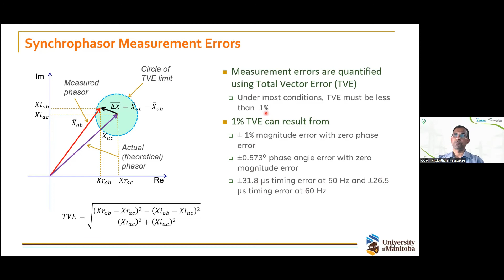To get some understanding of how tight the accuracy is, this 1% TVE can result even if the red line coincides with this one but there is a 1% error in the magnitude. On the other hand, if you have the same magnitude but a phase angle difference of 0.573 degrees, then it is exceeding the 1% error limit. This phase angle error corresponds to a 31.8 microsecond timing error for 50 Hertz, and for 60 Hertz it is even less than that: a 26.5 microsecond timing error can result in this error. So if you are building a PMU device, your time synchronization needs to be very, very accurate if you want to achieve this kind of accuracy level.